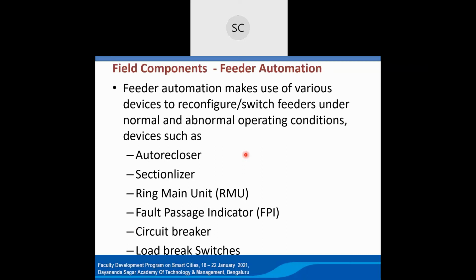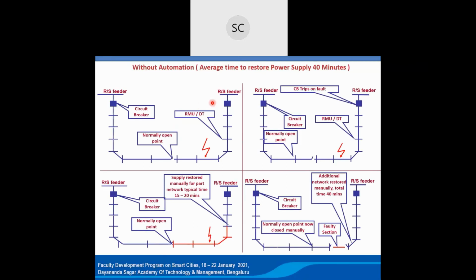Now, let us see through a diagram how feeder automation works. This is a typical system without automation. Here is the remote station feeder coming in. This is the circuit breaker, and there is one normally open switch. This slide is without automation. Then there is another RMU, or manually operated point, with a distribution transformer located in this area, and one more feeder from a remote substation.